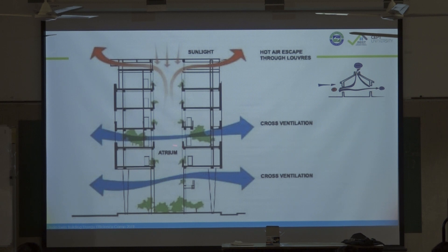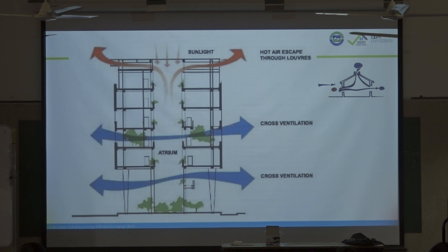This cross-section from the internet is exactly the same problem. Do you really think cross ventilation will work if you have an apartment here and another there? You'd have to ask your neighbor to open their door so you can use cross ventilation in your apartment. Honestly, the only option in that case is to create a low pressure shaft.